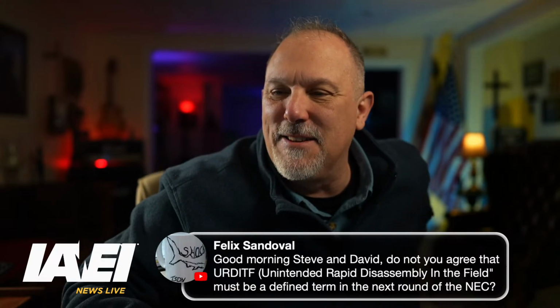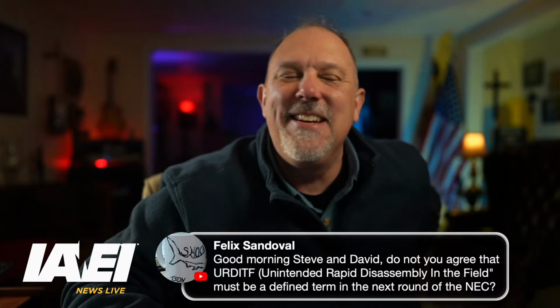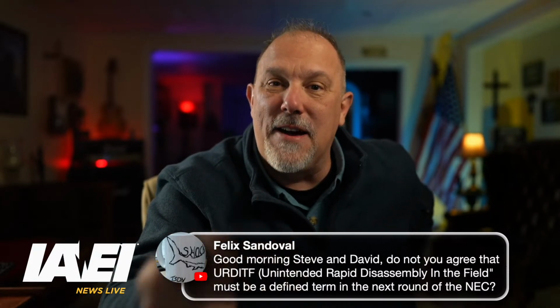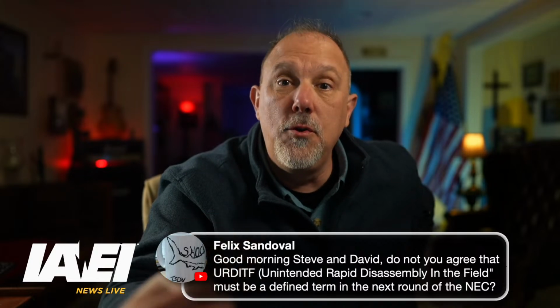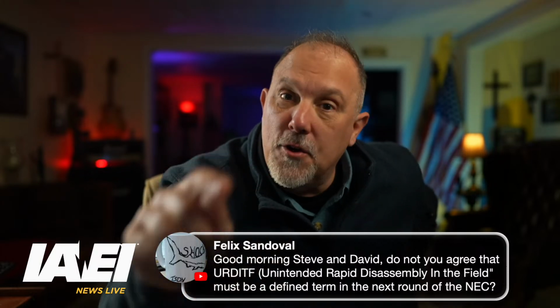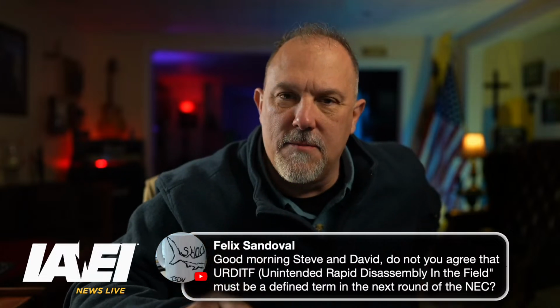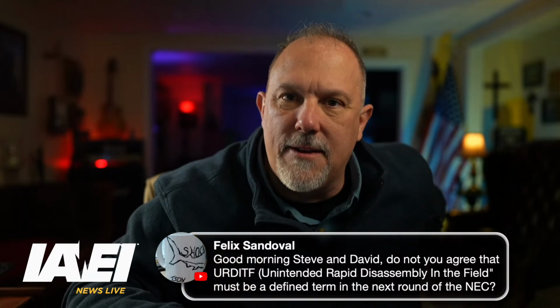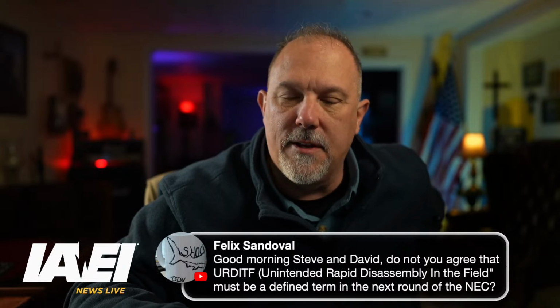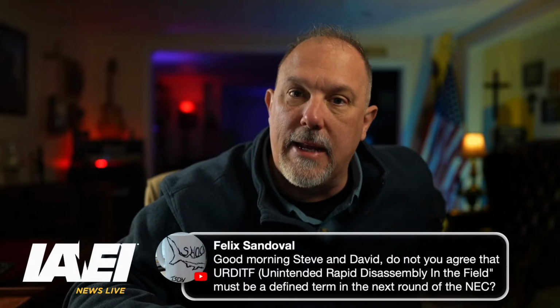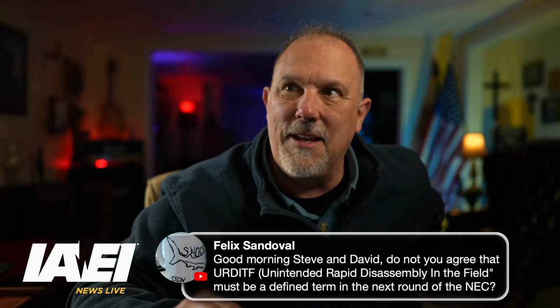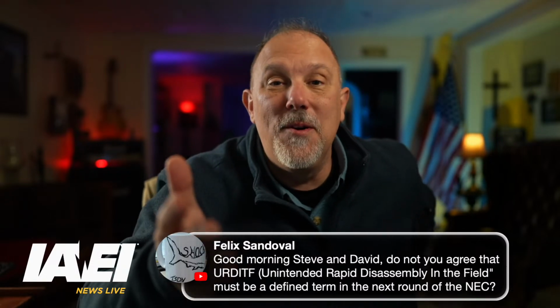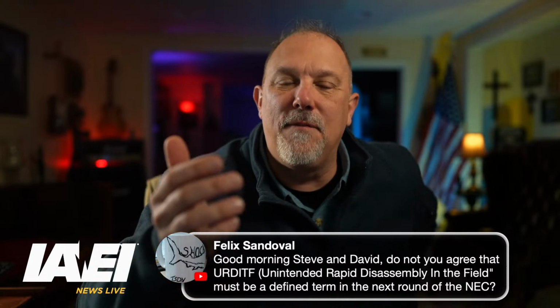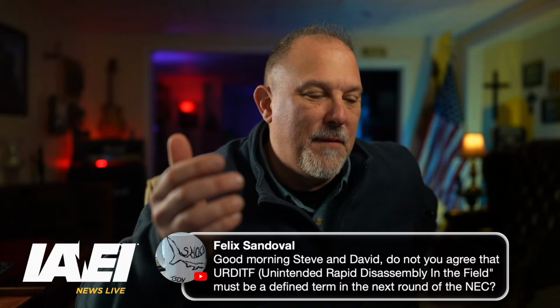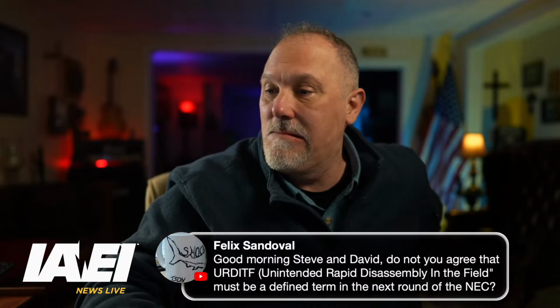Unintended rapid disassembly in the field must be a defined term. You know what, Felix, so here's the thing. If we're going to define the term, we have to use the term. So what we could do is put that terminology into Article 110.10 or the definition of what a short circuit current rating is. It's the beyond which, or no, we'll put it in the definition of fault current.